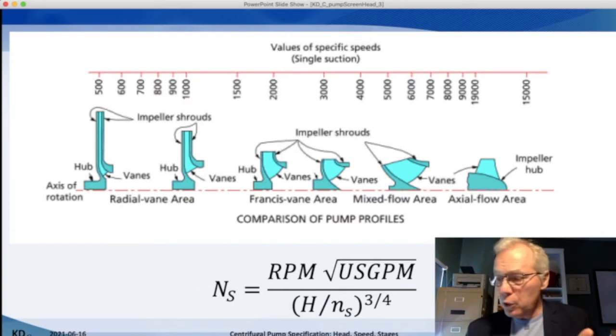This means that the specific speed is determined from our process conditions of flow rate and head, and our decisions on how fast the pump will run—the RPM—and the number of stages that we will have in the pump. So all we need to do is pick a speed and the number of pump stages that yields a workable pump.